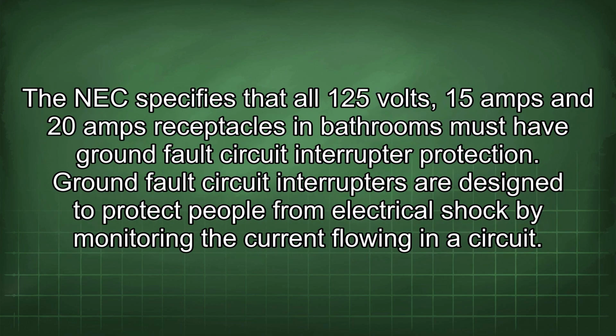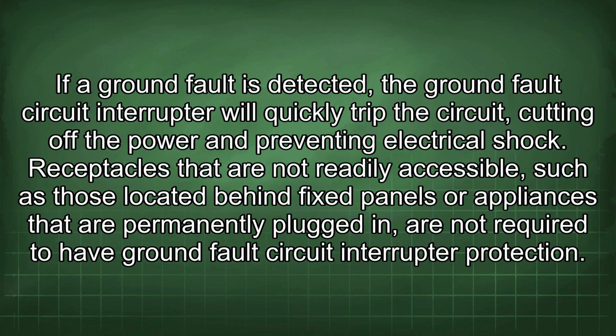The NEC specifies that all 125 volts, 15 amps and 20 amps receptacles in bathrooms must have ground fault circuit interrupter protection. Ground fault circuit interrupters are designed to protect people from electrical shock by monitoring the current flowing in a circuit. If a ground fault is detected, the ground fault circuit interrupter will quickly trip the circuit, cutting off the power and preventing electrical shock. Receptacles that are not readily accessible, such as those located behind fixed panels or appliances that are permanently plugged in, are not required to have ground fault circuit interrupter protection.